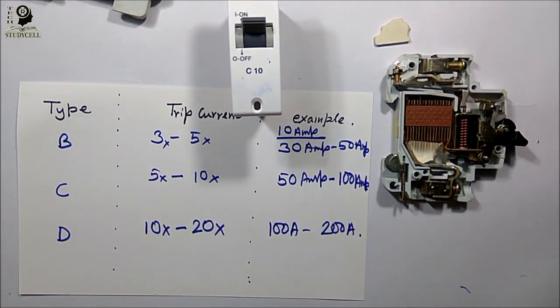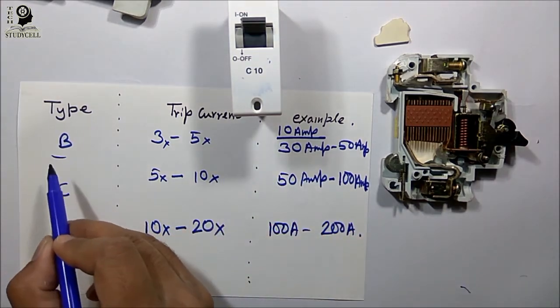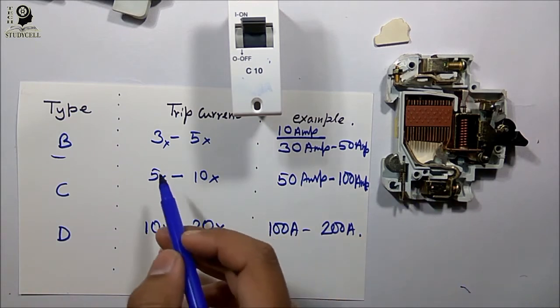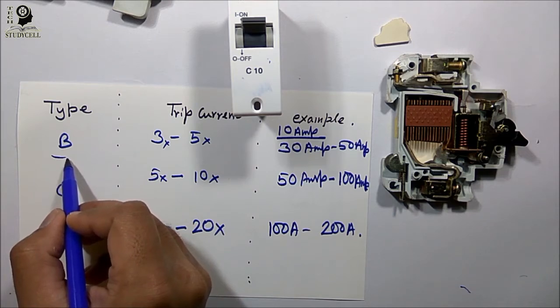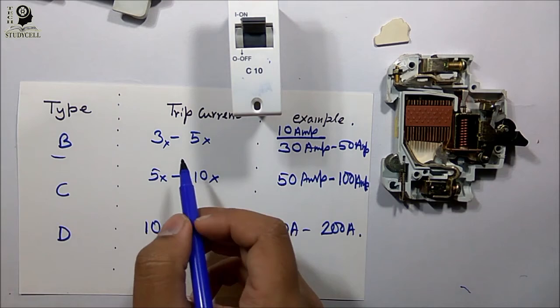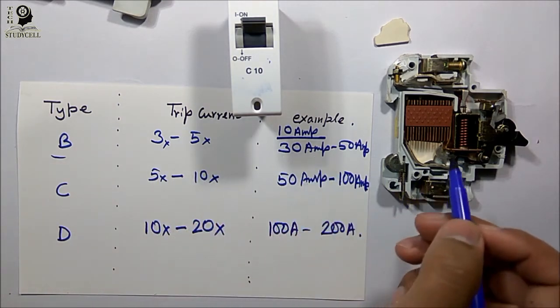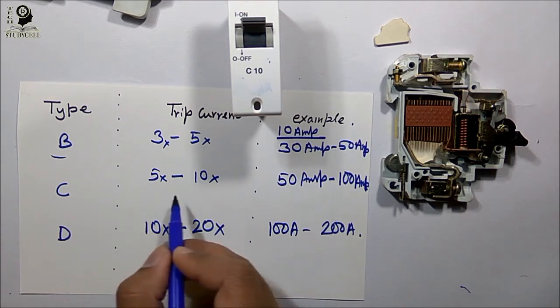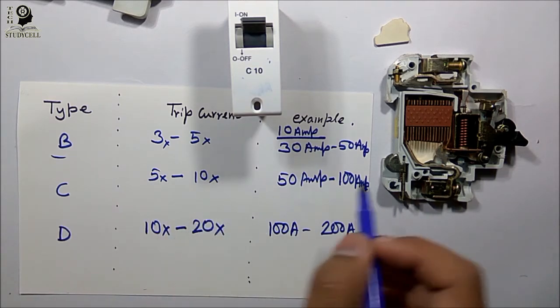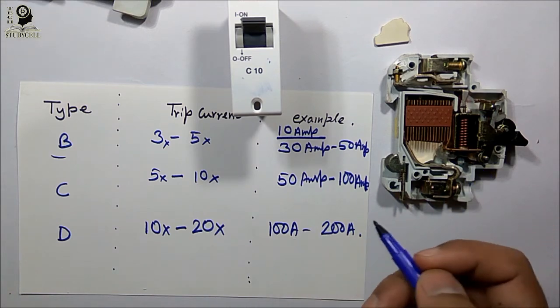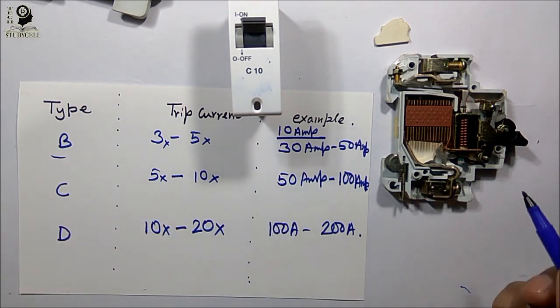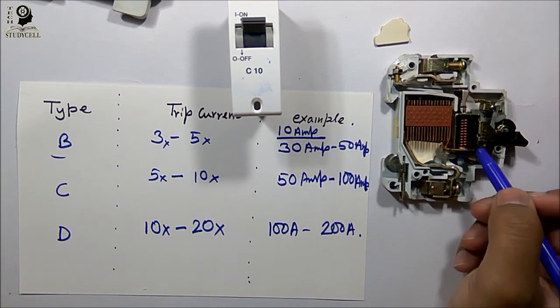Now if I supply a single phase induction motor through a B type circuit breaker, at the time of starting the motor will typically take 2 to 10 times its rated current. So B type will not be suitable for supplying a motor because it will trip instantly as the solenoid gets energized at starting. In that case we will use a C type circuit breaker, so that the solenoid will not get energized and trip the device at the highest starting current of the motor.